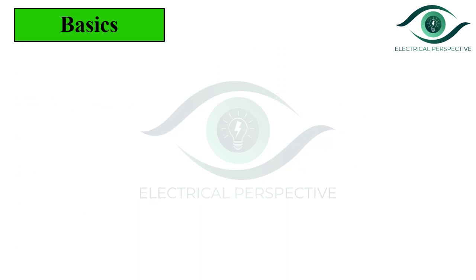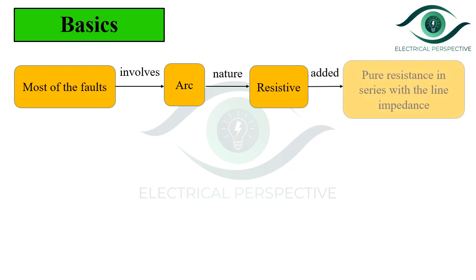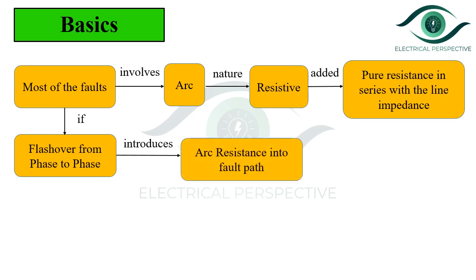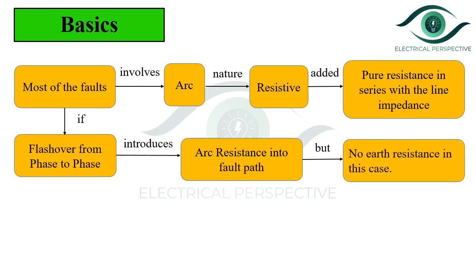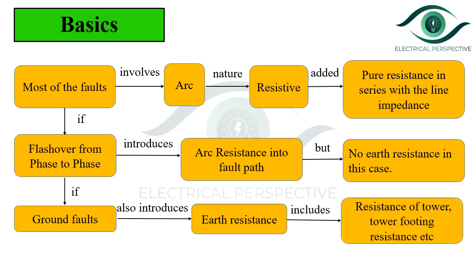Let us start with some basics. Most faults involve an arc which is resistive in nature and is added as a pure resistance in series with the line impedance. If flashover from phase to phase occurs, then it introduces arc resistance into the fault path but no earth resistance in this case. If a ground fault occurs, then it also introduces earth resistance, which involves resistance of the tower, tower footing resistance, etc.